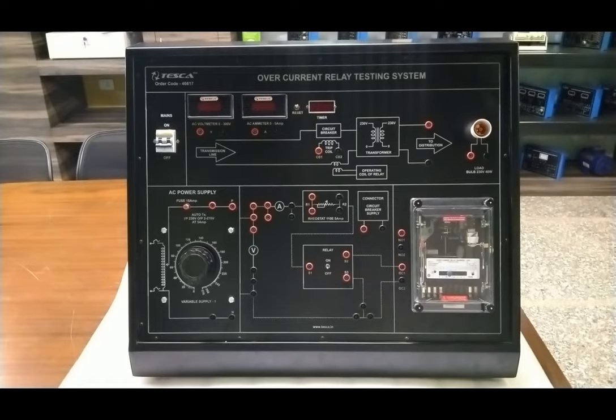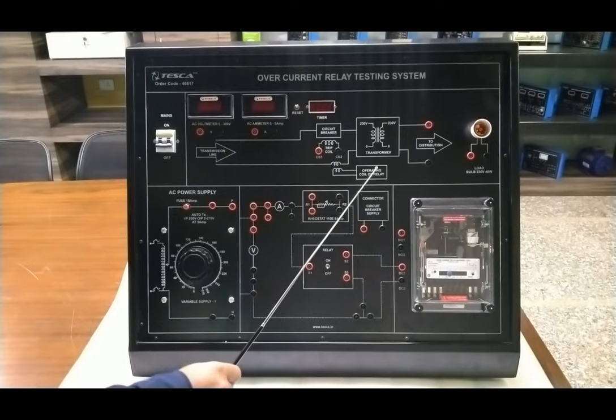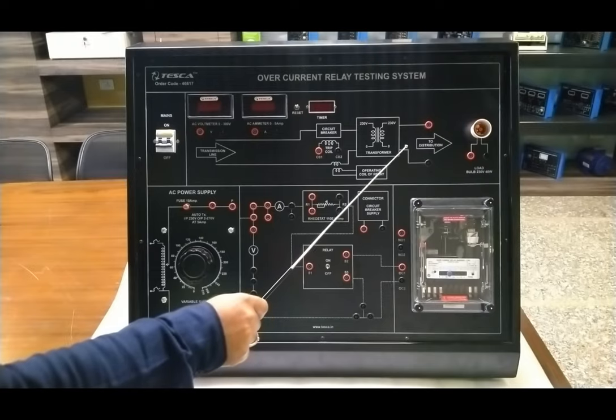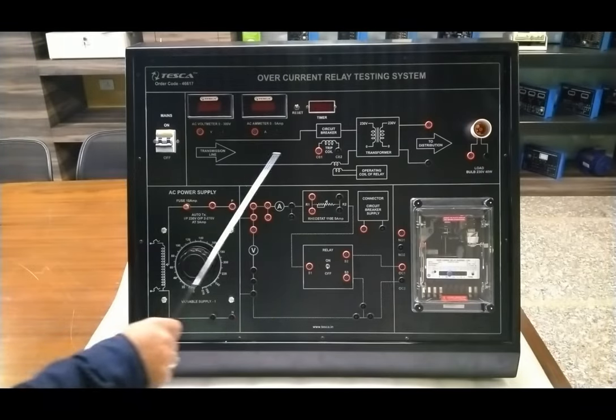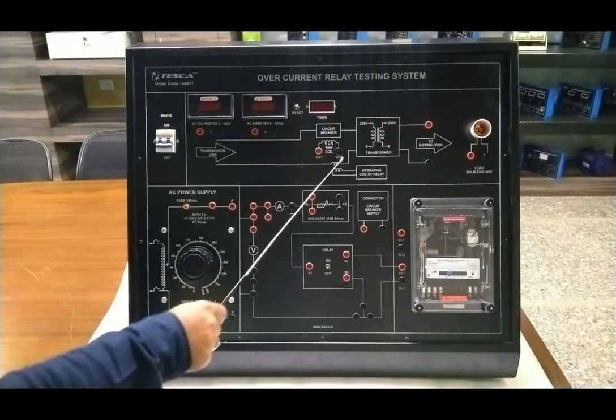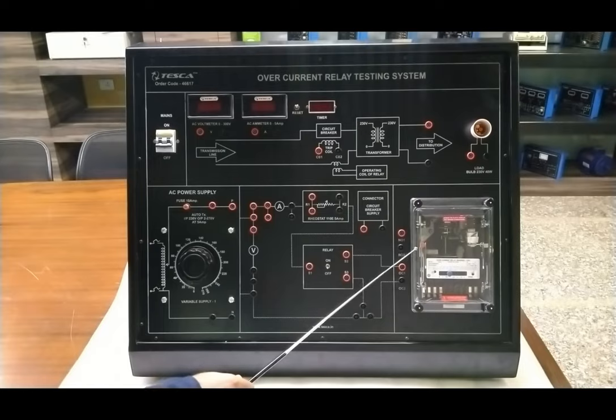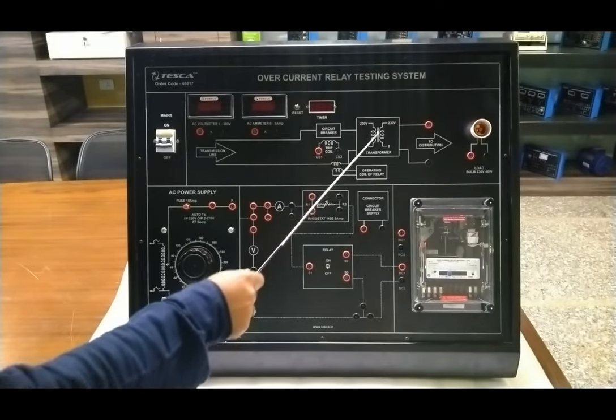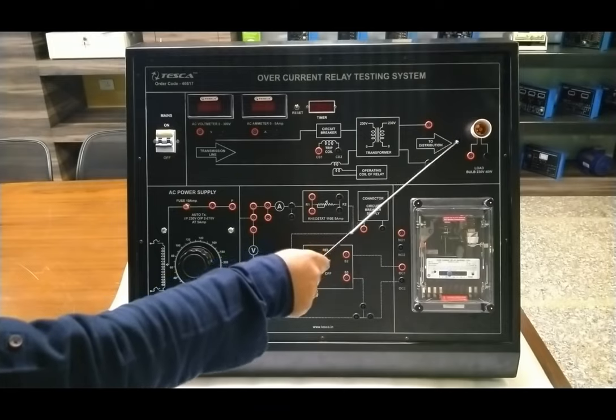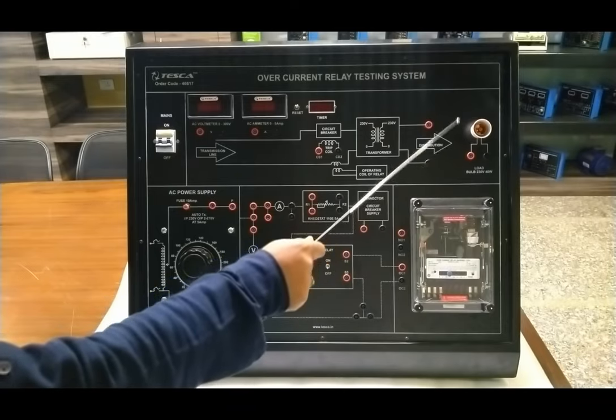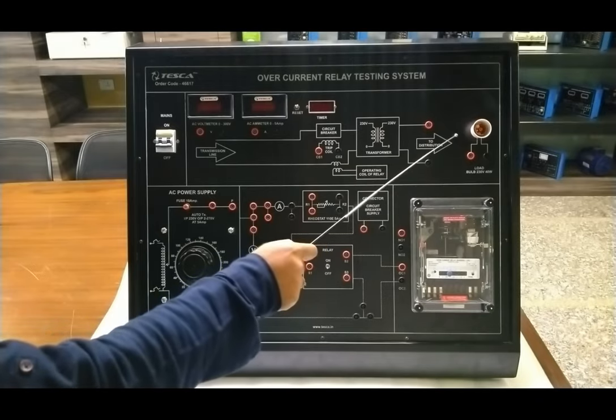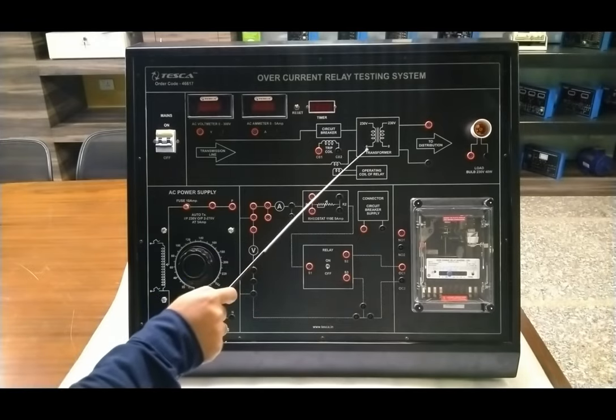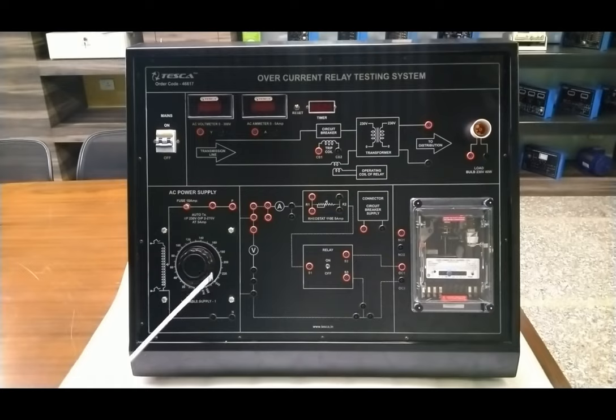For understanding the role of relays in a real-time transmission system, a circuit of a transmission line is provided from source to distribution with proper placement of all required components. The transmission line continuously goes through the circuit breaker, then there is a tripping coil connected with the overcurrent relay. The circuit breaker is connected to a transformer, and the transformer is directly coupled with the distribution to the load. We use a 40 watt bulb here at 230 volt power supply behaving like a load, connected with the transformer installed in this. The 230 volt power supply is also directly provided to the relay circuit.